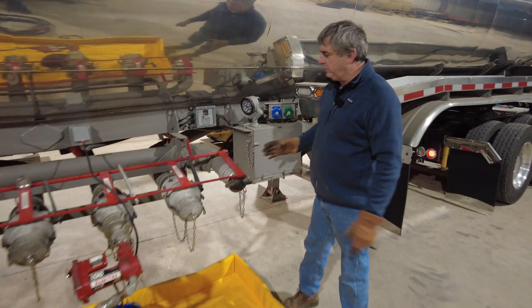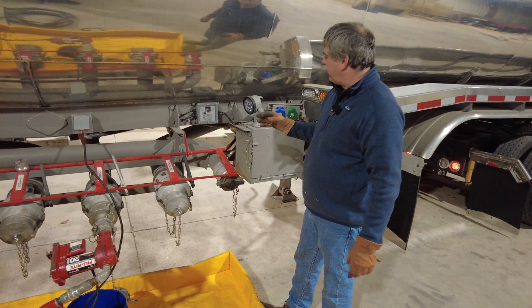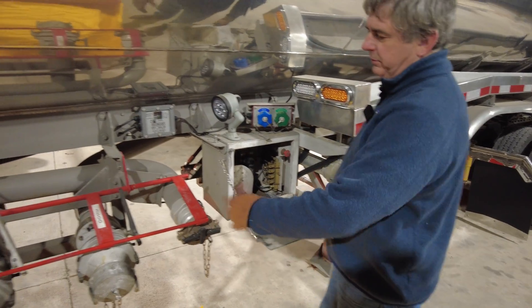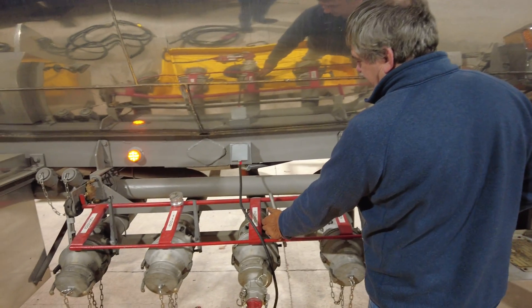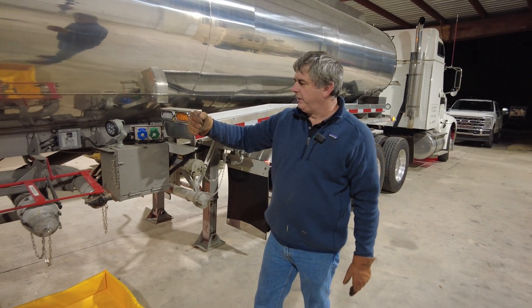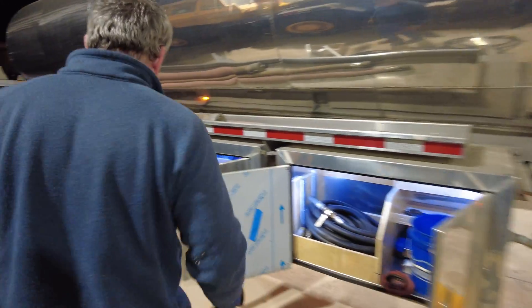For those wondering how it works when you see one of these trucks on the road — this tanker can hold around 9,000 gallons of fuel. The heads have valves on them but what's important is these trailers have belly valves underneath them. On this trailer, each compartment's belly valve is controlled by air. This is compartments one, two, three, and four — so for load head two, you move to that position and it opens the belly valve, letting fuel flow to the head. If you were to open the head right now, only what's left in that pipe would come out — it wouldn't empty the whole trailer. That's a key safety aspect of how the tanker trailer works. With this arrangement we can carry diesel and gas and fuel cars, generators, and big transfer tanks. When we arrive at a customer site needing two or three thousand gallons, we also have the large hoses traditional to the fueling industry — two-inch, three-inch, and four-inch hoses that connect from the load head.